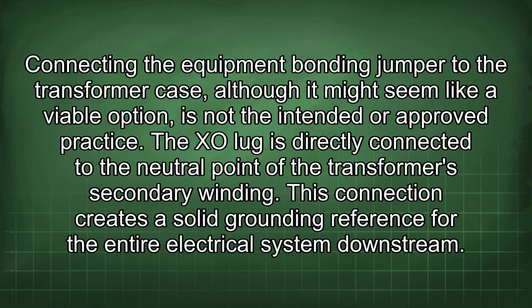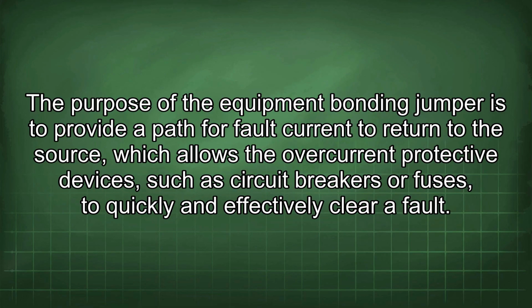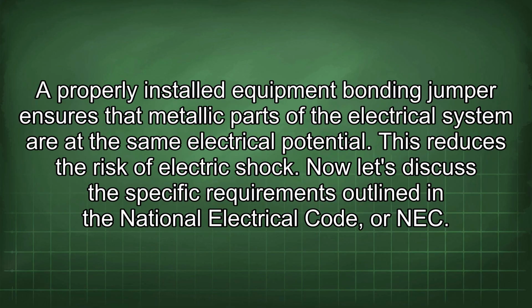intended or approved practice. The XO lug is directly connected to the neutral point of the transformer secondary winding. This connection creates a solid grounding reference for the entire electrical system downstream. The purpose of the equipment bonding jumper is to provide a path for fault current to return to the source, which allows the overcurrent protective devices, such as circuit breakers or fuses, to quickly and effectively clear a fault. A properly installed equipment bonding jumper ensures that metallic parts of the electrical system are at the same electrical potential. This reduces the risk of electric shock.